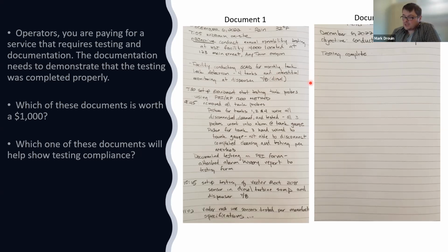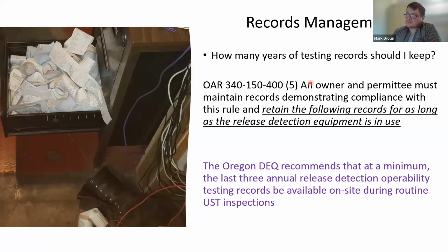Another question that comes up a lot during inspections is, how long do I keep these records? This varies, our rules, a couple different parts talk about different things. For this operability testing, we say, well, as long as that probe is in use, you got to keep that testing record. So let's say this probe has been used for 20 years and you've been testing it for 20 years, you should be keeping 20 years of records.